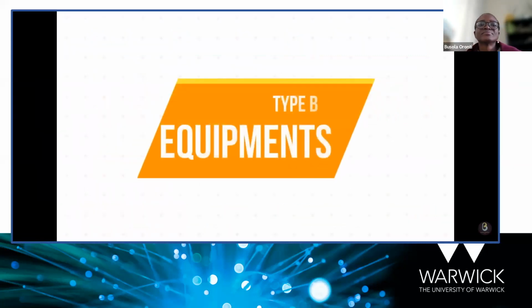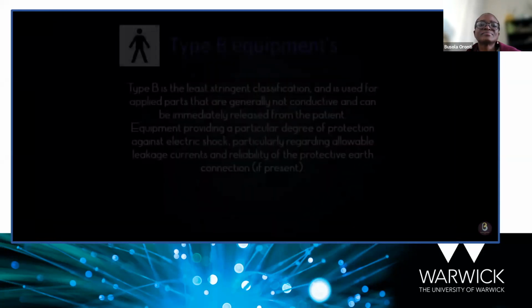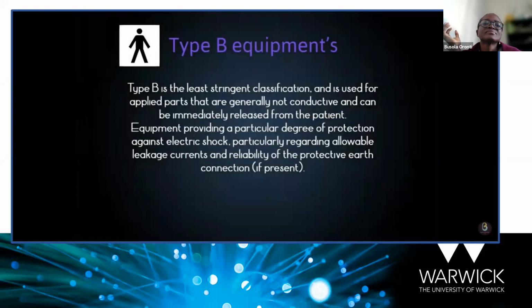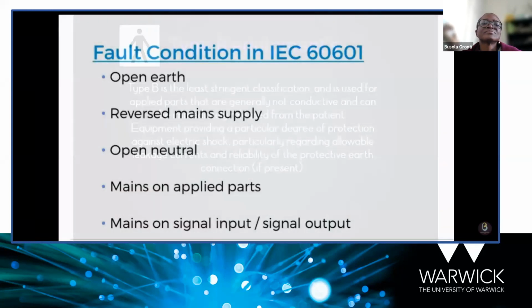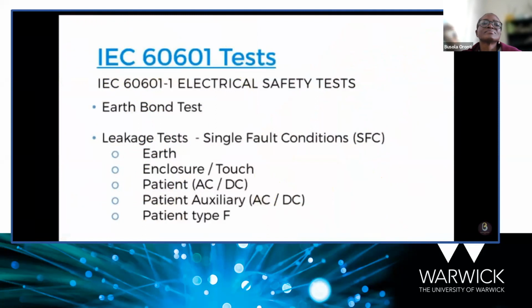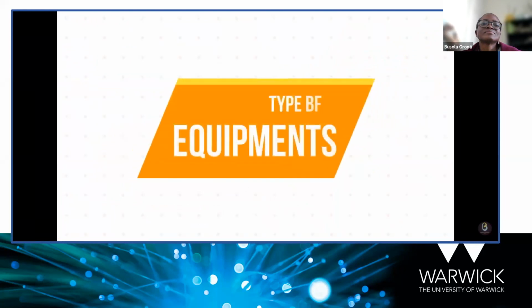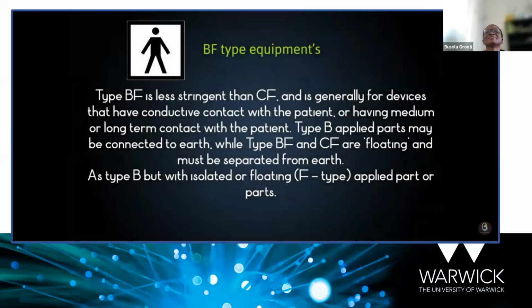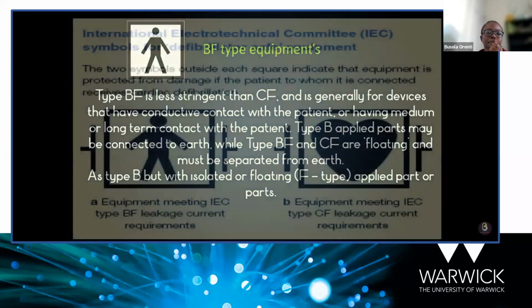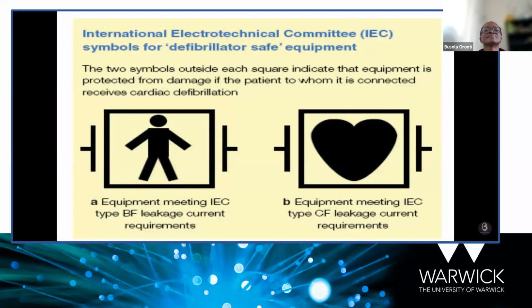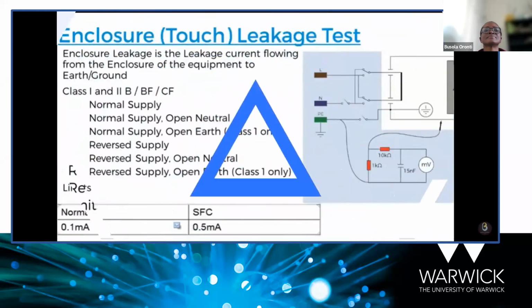Let's begin know about Type B equipment. Type B is the least stringent classification and is used for applied parts that are generally not conductive and can be immediately released from the patient. Equipment providing a particular degree of protection against electric shock, particularly regarding allowable leakage currents and reliability of the protective earth connection, if present. The next type is BF type equipments. Type BF is less stringent than CF and is generally for devices that have conductive contact with the patient or having medium or long-term contact with the patient. Type B applied parts may be connected to earth, while Type BF and CF are floating and must be separated from earth as Type B, but with isolated or floating F-type applied part or parts.